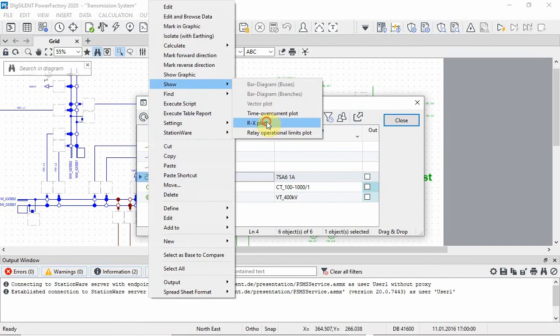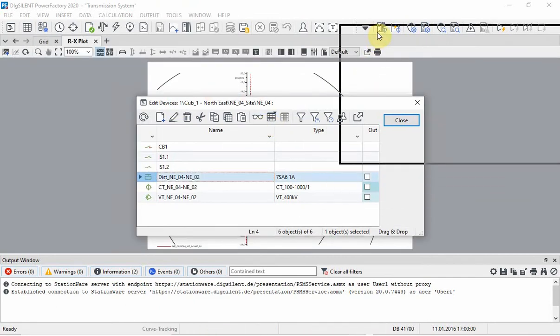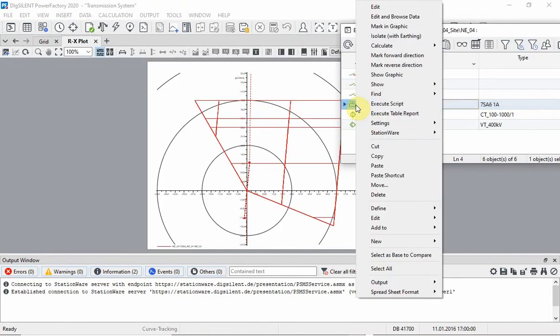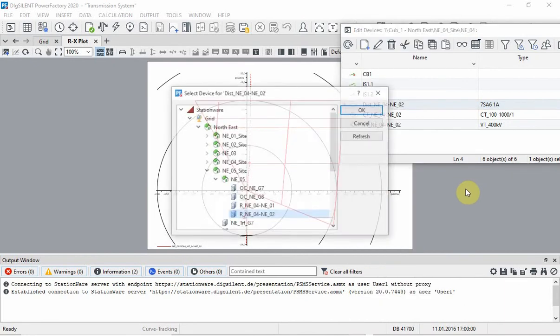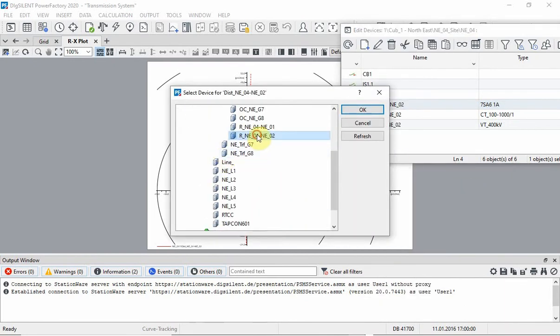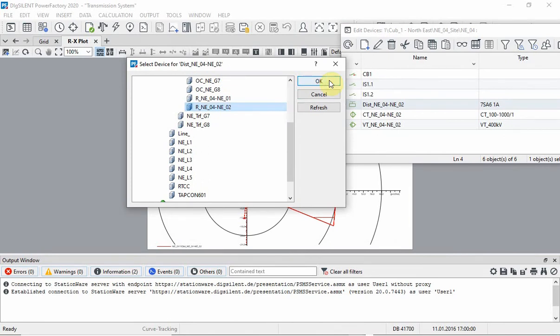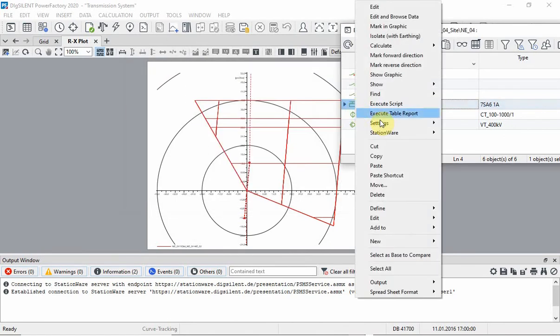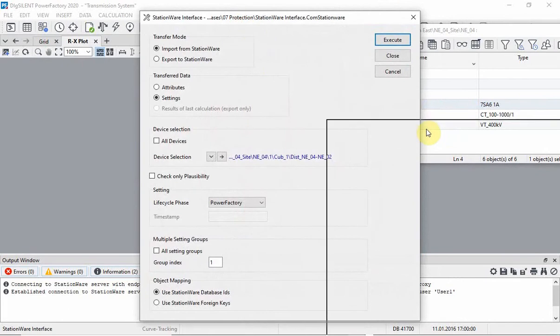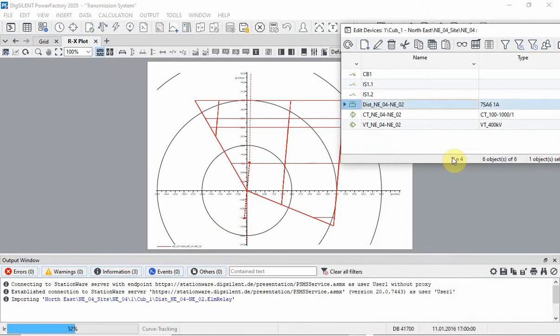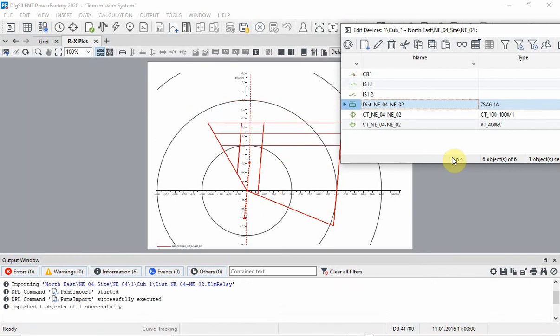We will show our RX-Diagram for this relay. Let us link the PowerFactory relay device and the Stationware relay and import the settings. Notice how the RX-Diagram automatically changes. Let us compare the imported values with the ones in Stationware.